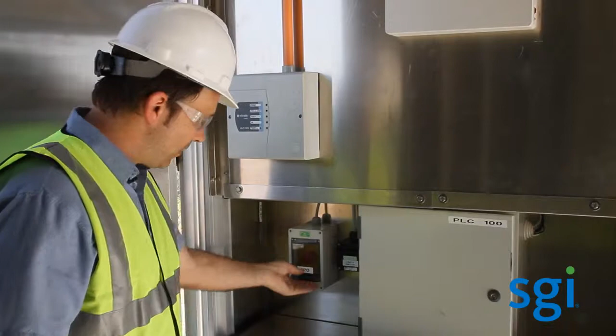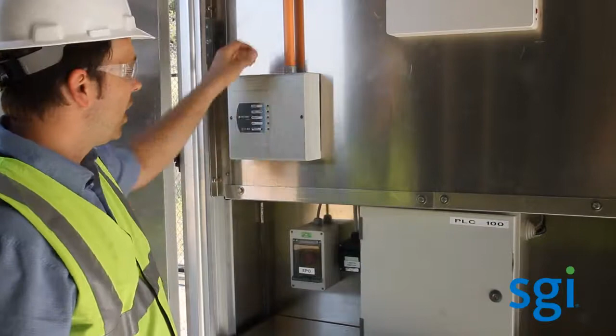Typical in a data center, you have an EPO button which shuts off everything in the entire unit—that's connected to the monitoring control system as well. You have the VESDA fire detection system, with sniffers that are technically sensors for smoke. Throughout the unit there are temperature and humidity sensors placed strategically, and down below there's leak detection placed strategically throughout, just in case.